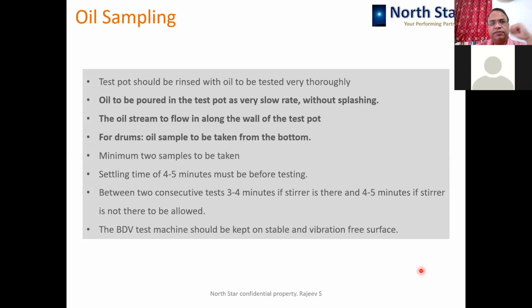When we talk about oil testing, oil sampling plays a very important part, and our team normally observes that sampling is not done rightly, and a wrong sampling is as bad as not doing the test on the transformer, or even worse than that, because when you wrongly sample the oil, the test results give you something else which is actually not the situation, and you are unnecessarily panicking with the wrong test results and leading to unwanted actions on your equipment. So sampling is the starting point of diagnosis of the transformer insulation.